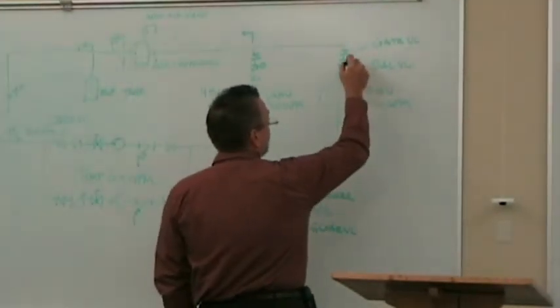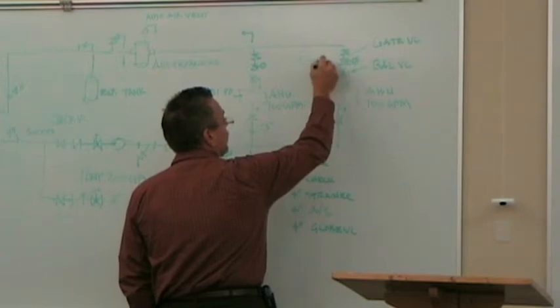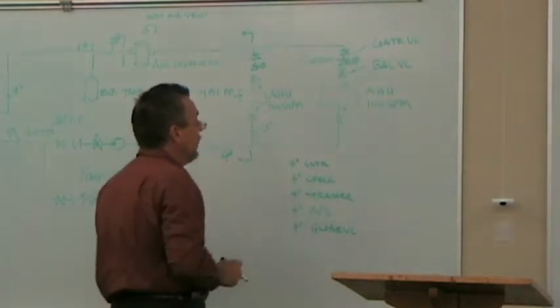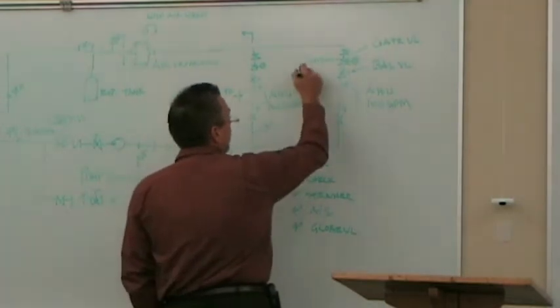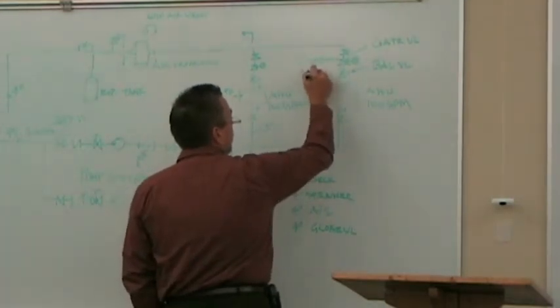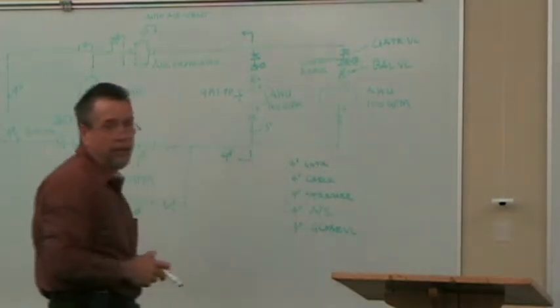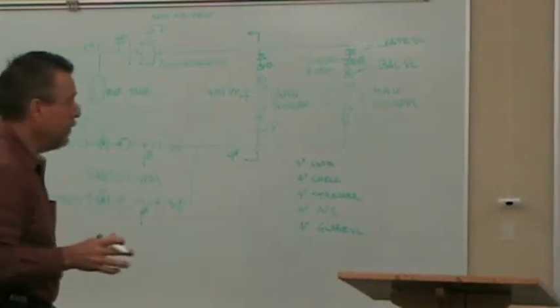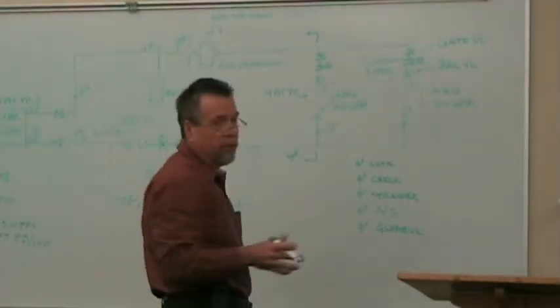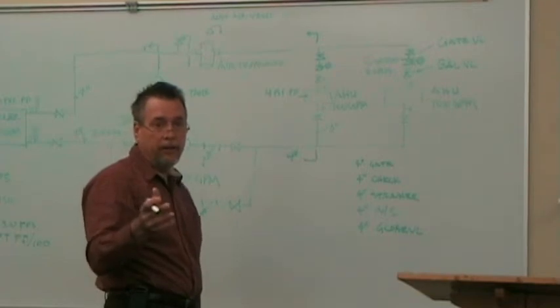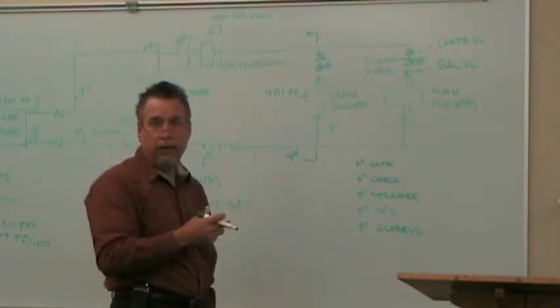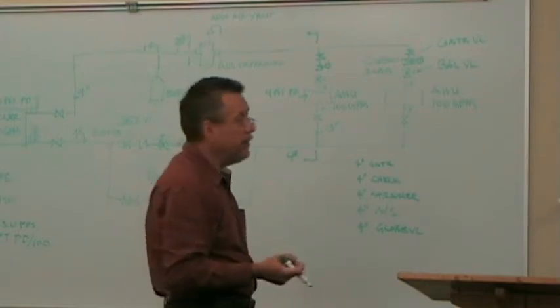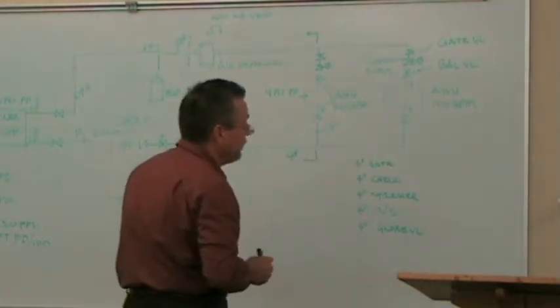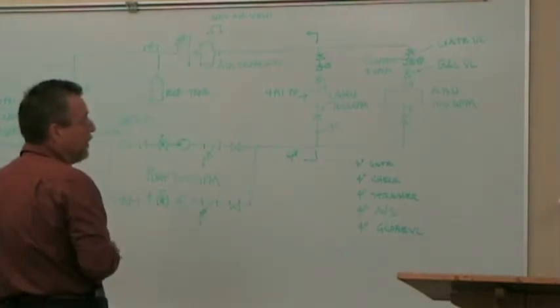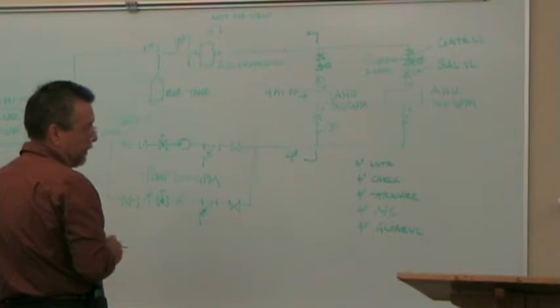Okay, mostly, now I know that I specified this control valve with a certain pressure drop so that the controls contractor can select the valve. And I want that to be 3 PSIG. I want the control man to select a valve that has a 3 PSIG drop. That way I know that the valve is going to be adequately sized and have enough pressure drop to work correctly. Get too large a valve, the valve cracks open, you can't control the flow. Too small a valve, you're not going to get enough flow through the control valve. But a 3 PSI valve will give me approximately a good selection on a valve that I know would work.